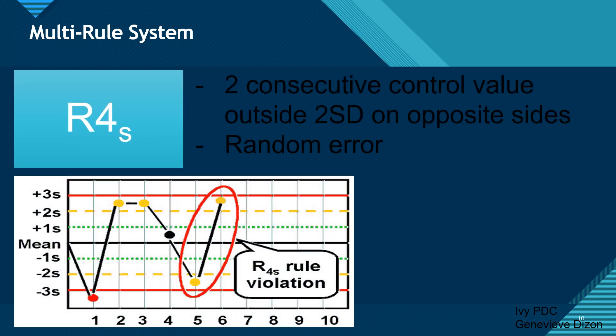The R-4-S rule means there are two consecutive control values outside the 2-SD, but on opposite sides — one on the positive side and one on the negative side, both outside the two standard deviations. This is considered a random error since the results are not on the same side. One control measurement exceeds the positive two standard deviations and another exceeds the negative two standard deviations. We also reject the results coming from these controls.